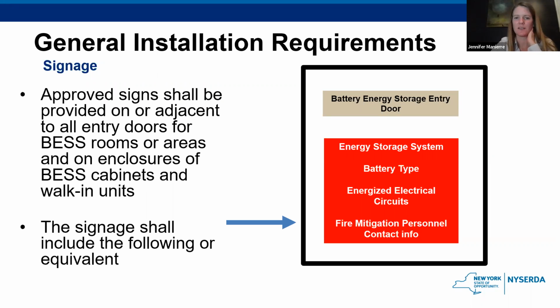There are signage requirements all across the board. There needs to be approved signage on all the entry doors to the energy storage rooms or areas, or on the outside of the enclosures if you have energy storage cabinets or outdoor walk-in units. Signage is going to tell you what's in there. It's an energy storage system. It will tell you what type of battery it is, perhaps lithium ion, maybe lead acid, or one of the other types. It should clearly state that there are energized electrical circuits. And then critically, at the bottom of the little graphic there, the fire mitigation personnel contact info. You always want to make sure that any first responders that are showing up can call up someone who really knows the system inside and out and can help guide them through what to do in the event of an incident.